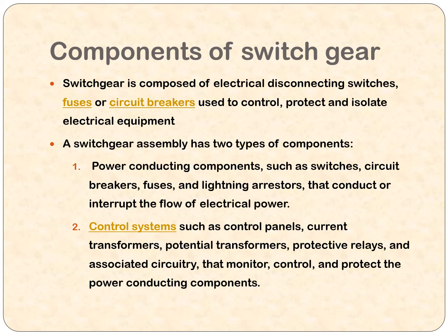These three parameters may look the same, but each has its own character. Based on that, the switchgear assembly has two basic areas. One is power conducting components like switches, which are switched on and off to make power flow from source to load, and circuit breakers, fuses and lightning arresters, which are all safety equipment for hard switching, that is, switching off the circuits. So it will interrupt the flow of electric power.